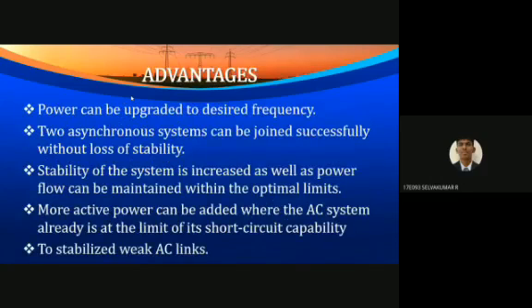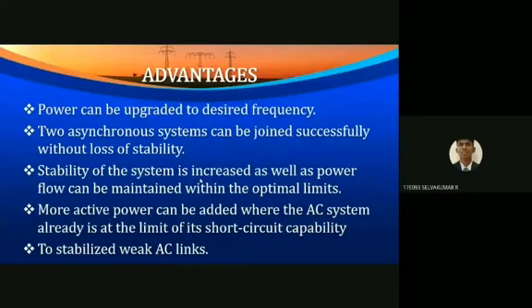The advantages of back-to-back stations are: power can be upgraded to the desired frequency; two asynchronous systems can be joined successfully without loss of stability; more active power can be added where the AC system is already at the limit of its short circuit capability; weak AC links are stabilized; and stability of the system is increased with power flow maintained within optimal limits.